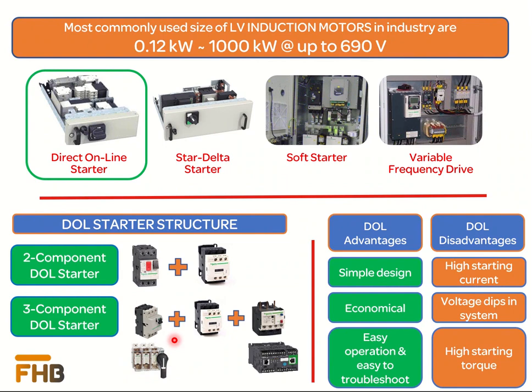Thermal protection is through a thermal overload relay, and the magnetic contactor is used to control the motor starting based on defined logic. In the case of a digital starter, the thermal overload relay is replaced with the motor controller. This controller provides protection, metering, and monitoring for the connected motor.